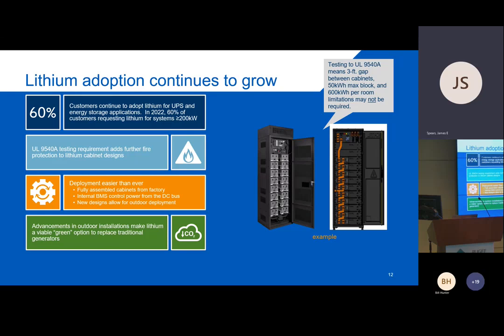The other thing was the UN 38.3 shipping requirements were such that 4 years ago, most of the vendors were not able or allowed to ship a battery cabinet with the batteries already installed. Even if they weren't connected together, just with the batteries on the shelves, they weren't rated to do that.